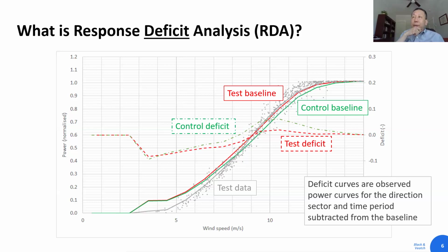It's also curious because in that case, we don't really know the underlying ground truth. From this moment onward, a set of vortex generators was put on the blade of the test turbine, and they basically want to know how much effect that VG will have in terms of improving the performance of the test turbine. Yeah, so this was why I had this question about the fact that the control baseline is performing less well than the test baseline when it should be the other way around.